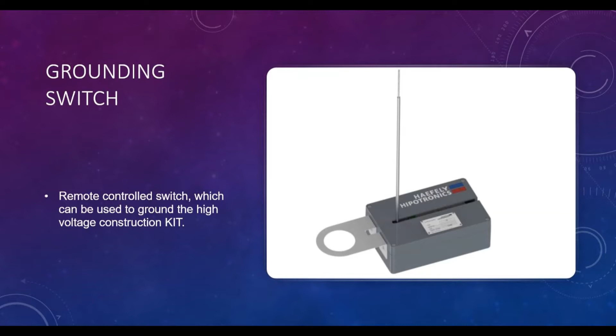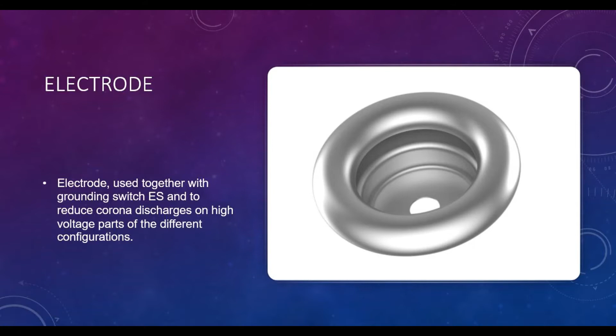My name is Kuganesh and I'm going to explain about the electrode. Electrode is used together with the grounding switch, which is ES, to reduce corona discharge on high voltage parts of different configurations. For example, for AC 2 or 3 stages, a top electrode on the test transformer is recommended to avoid corona effects too.